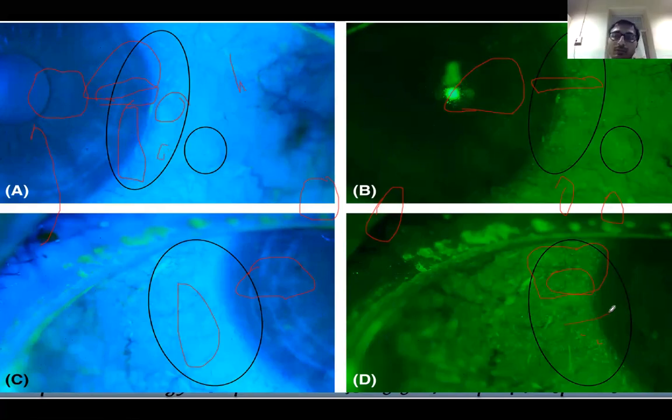So this yellow filter is very effective when, with the fluorescent stain, you want to examine a conjunctival surface. With the fluorescent stain, you want to examine a conjunctival surface, the yellow filter scores much above your blue filter. But on the cornea, blue filter is sufficient. But for the surface, the fluorescent is best with the yellow filter.